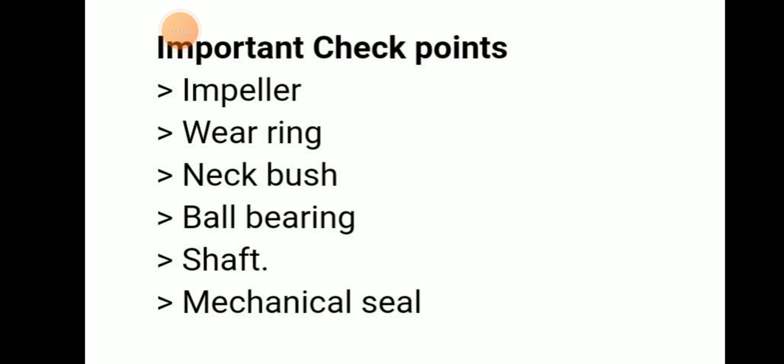The checkpoints during overhauling are: impeller, wear ring, neck bush, ball bearing, shaft, and mechanical seal. These are the key checkpoints to inspect while overhauling a centrifugal pump.